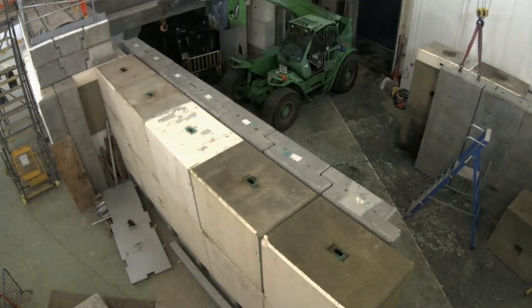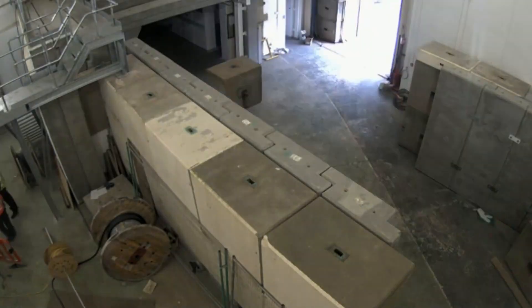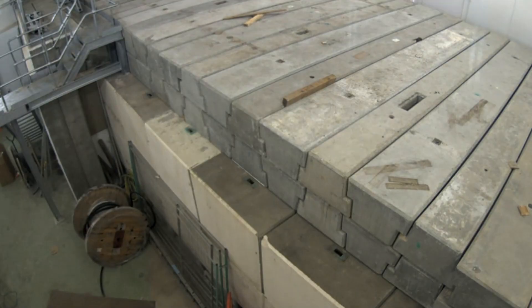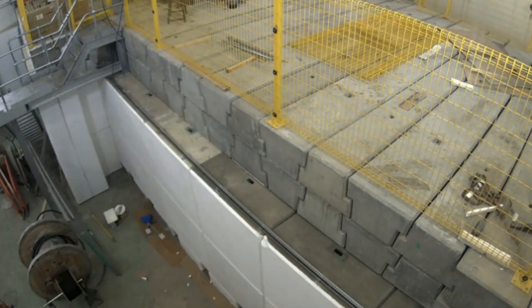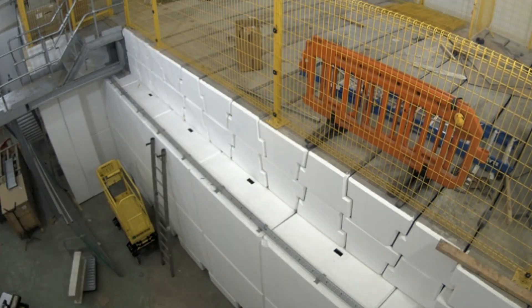Because AVO's light system uses linear acceleration, there's a considerable reduction in the shielding that's required and no need for absorbers to handle stray excess radiation found with legacy cyclotron systems. This is a major advantage of the system, making it far easier and more affordable to install.